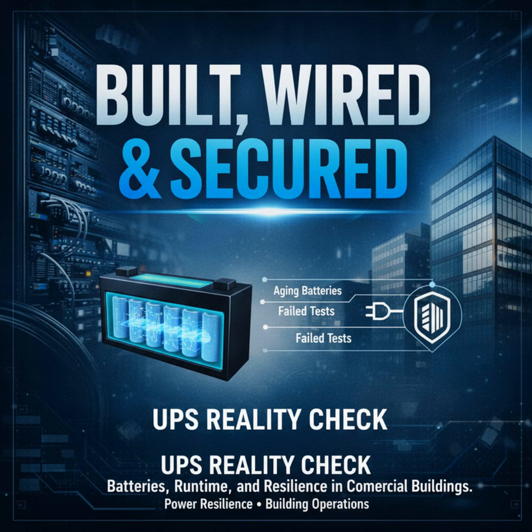Expert examples. 2 quick lessons from the field. Michael, give us a low-cost mitigation and a capital-level correction that changed outcomes. Low-cost mitigation. We added distributed UPS modules to a handful of comm closets that hosted tenant access control and payment terminals. The modules were inexpensive, monitored remotely, and cut outage complaints by 80% for a single-digit % of the original capital estimate.